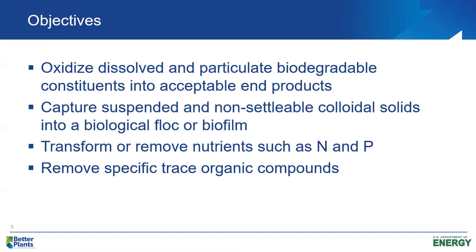But the thing you need to understand is the size of the particle is very important in determining how we will remove it from the wastewater. We'll have suspended solids. Again, as I explained in the first presentation, suspended solids are greater than about 1 or 1.2 microns. And in raw municipal wastewater, we'll have a moderate concentration of what I call inert suspended solids. Inert means they're not going to be biodegradable. But we can still remove those suspended solids because they will get bound up in the biological floc and actually settle in the settling basin.